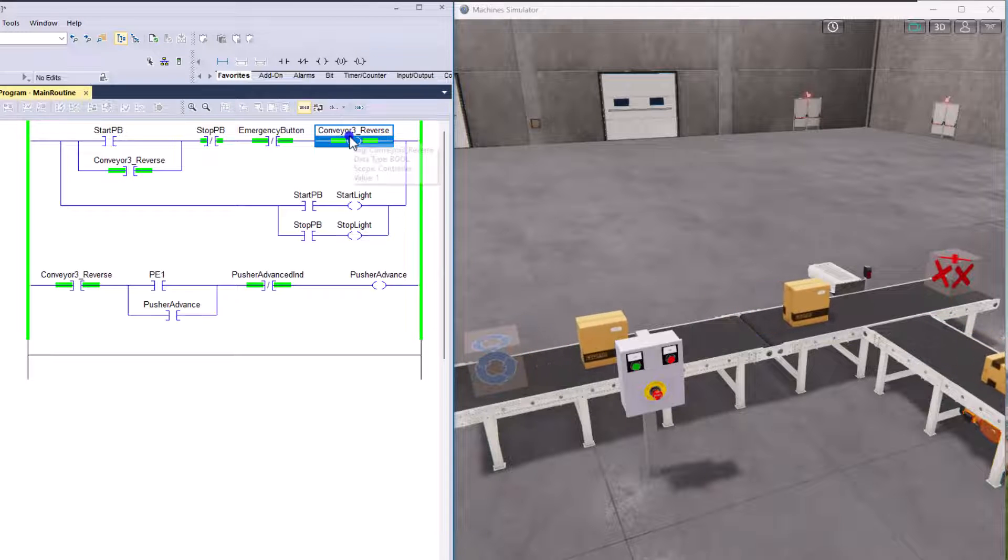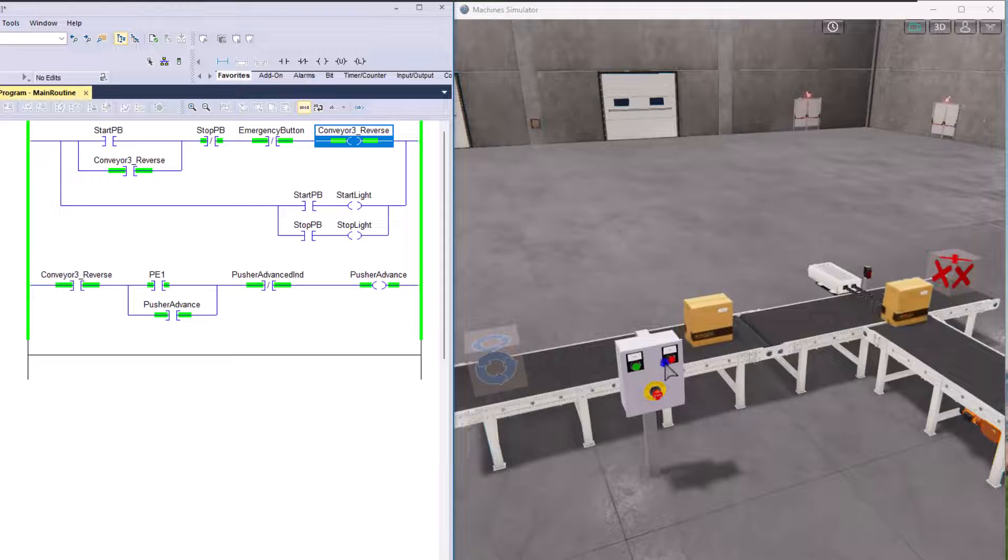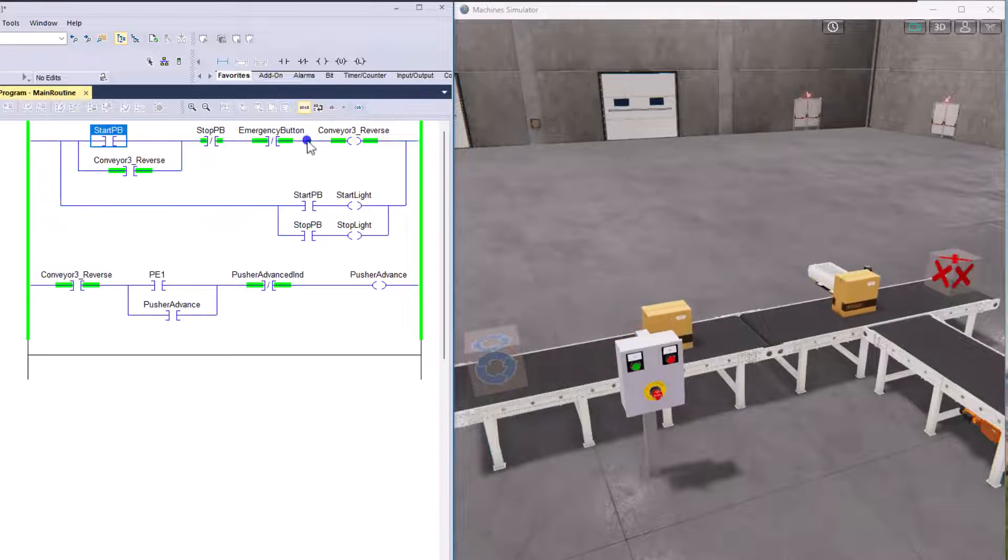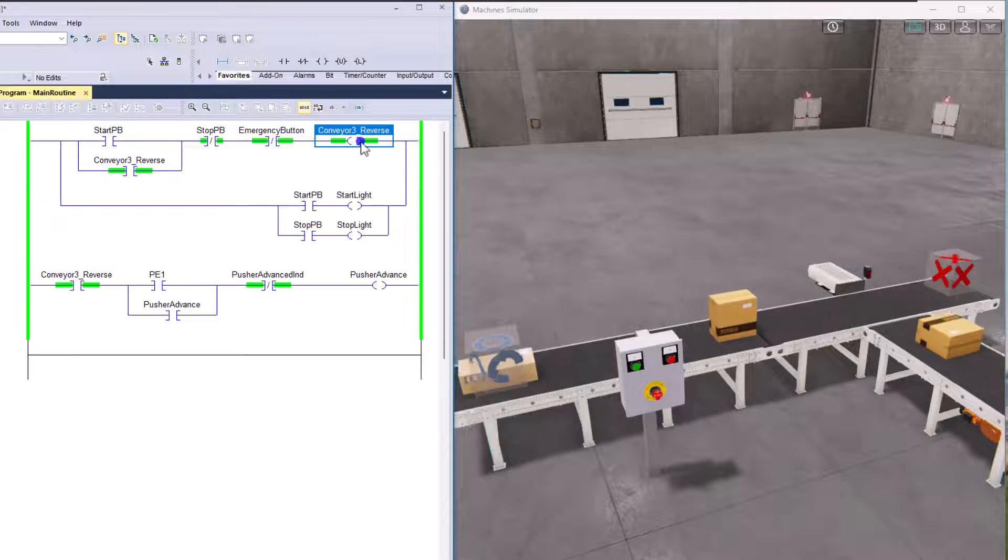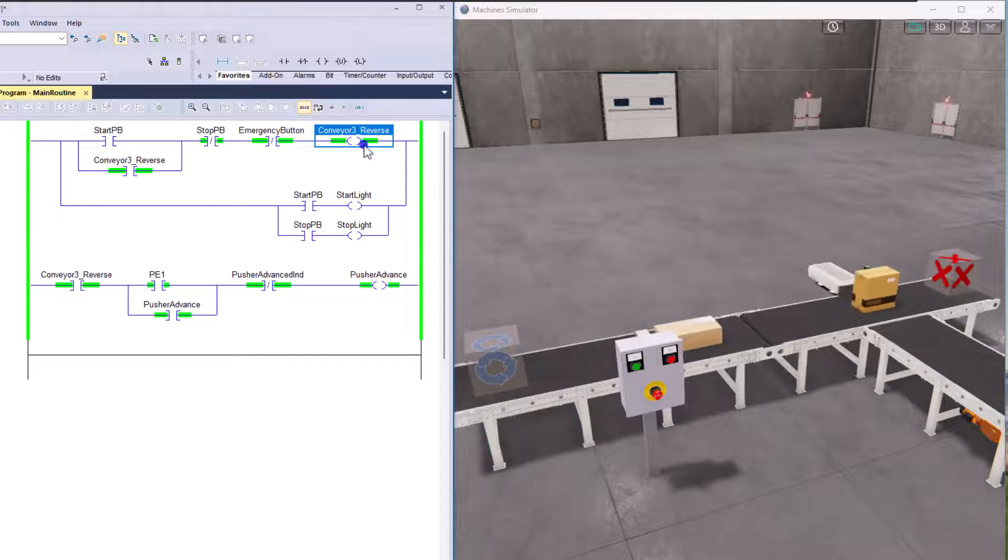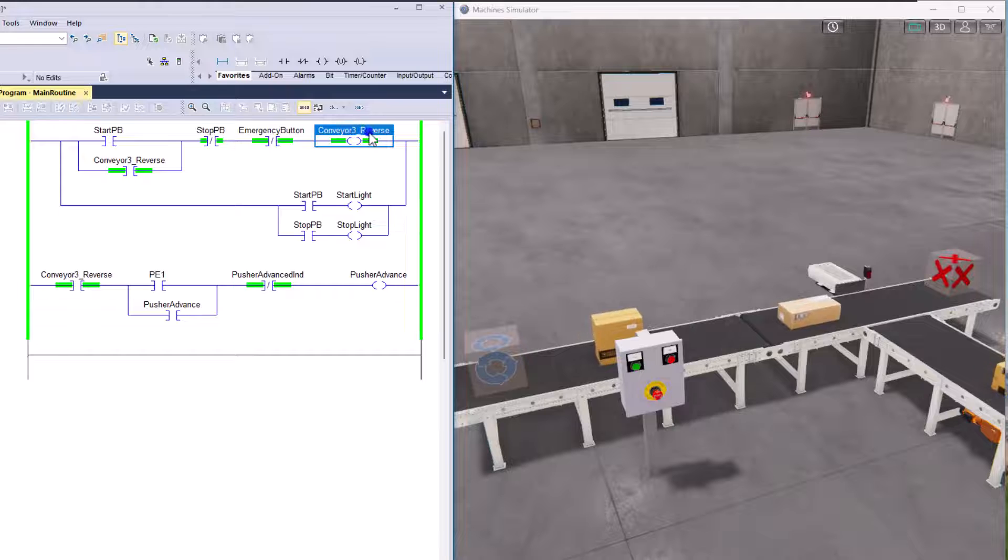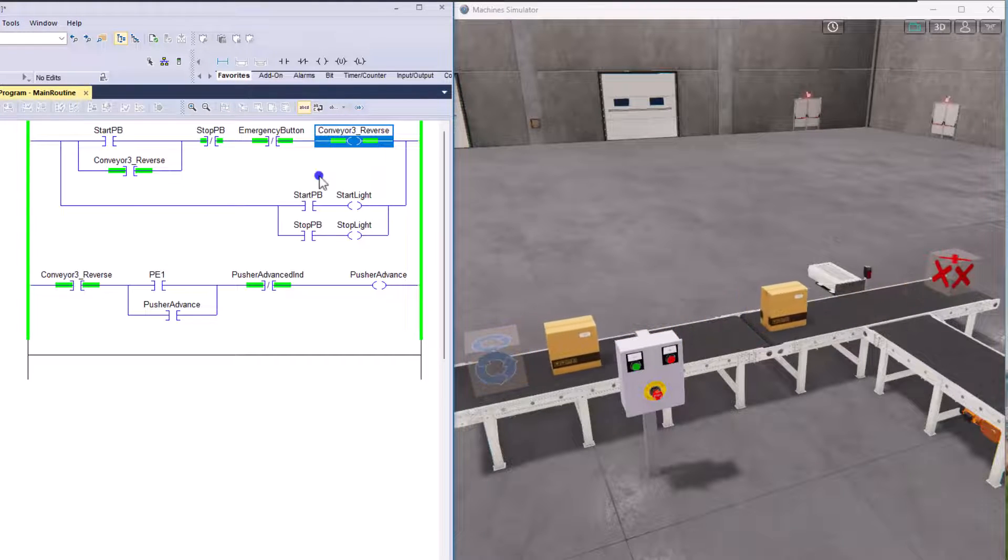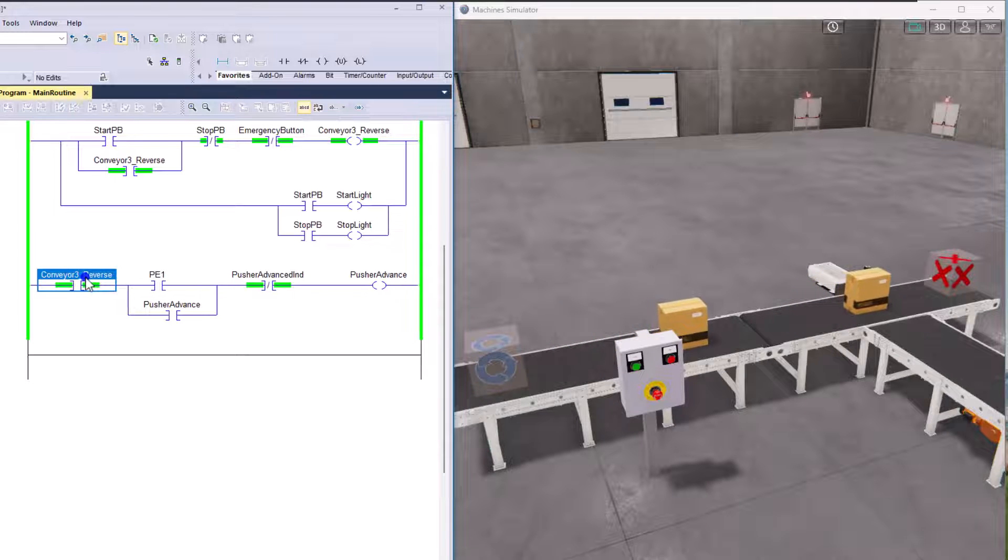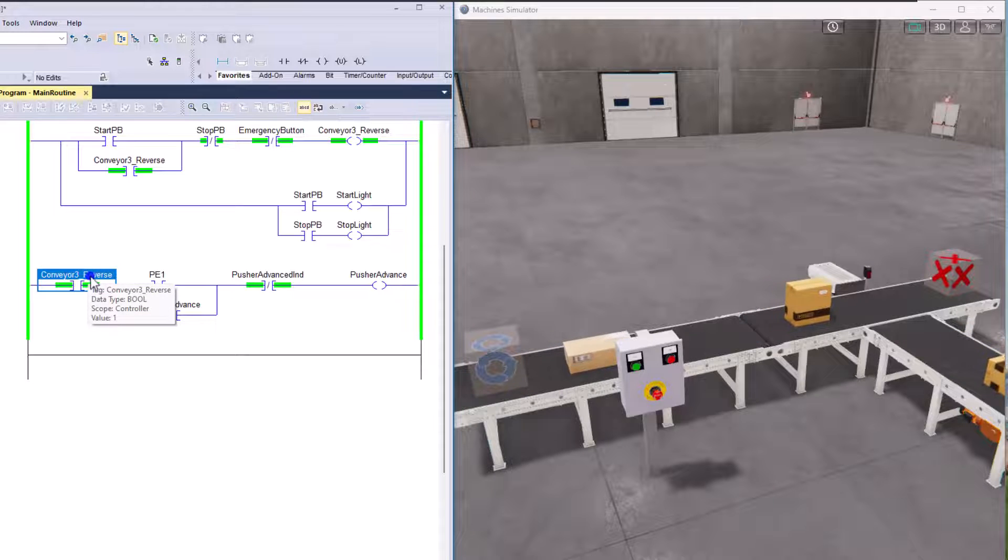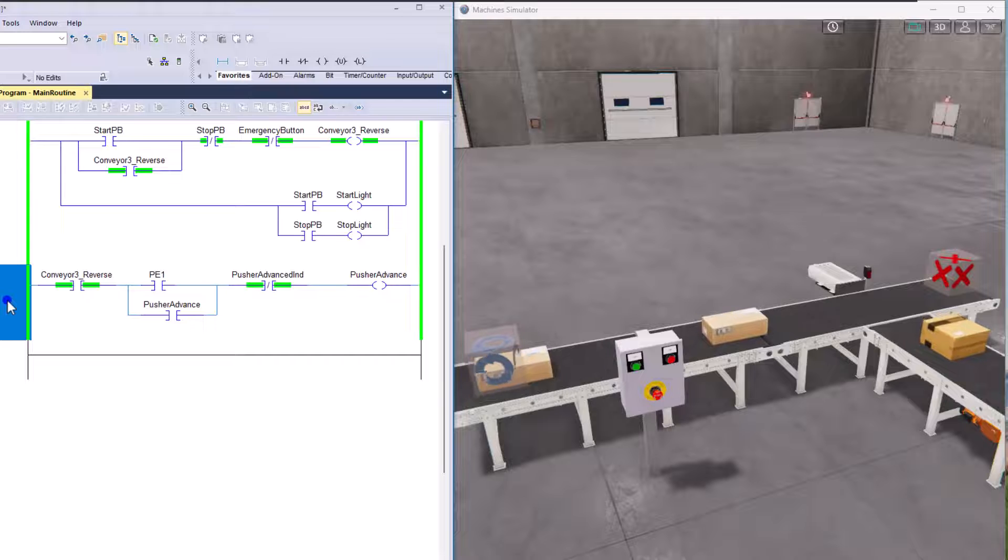And again, you can use a tag. These are all controller tags. These are all controller tags. And basically, all the controller tags, the possibilities are basically endless as far as that goes. Meaning if I'm using conveyor three underscore reverse right here and I'm controlling that with the OTE, I can use that same bit in an XIC or XIO to actually utilize that to control something else. In rung one, that's what we're doing.